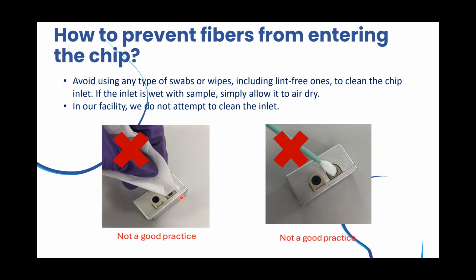Another quick piece of advice is to not put any liquid drops into the ports as well. You may be tempted to do that, but you shouldn't. One time I actually sprayed solvent into an inlet and ended up destroying the sensors. So that's another good practice to follow, not to spray any liquid into the ports. Simply allowing the chip cleaning station to clean your chip is a good practice to follow.